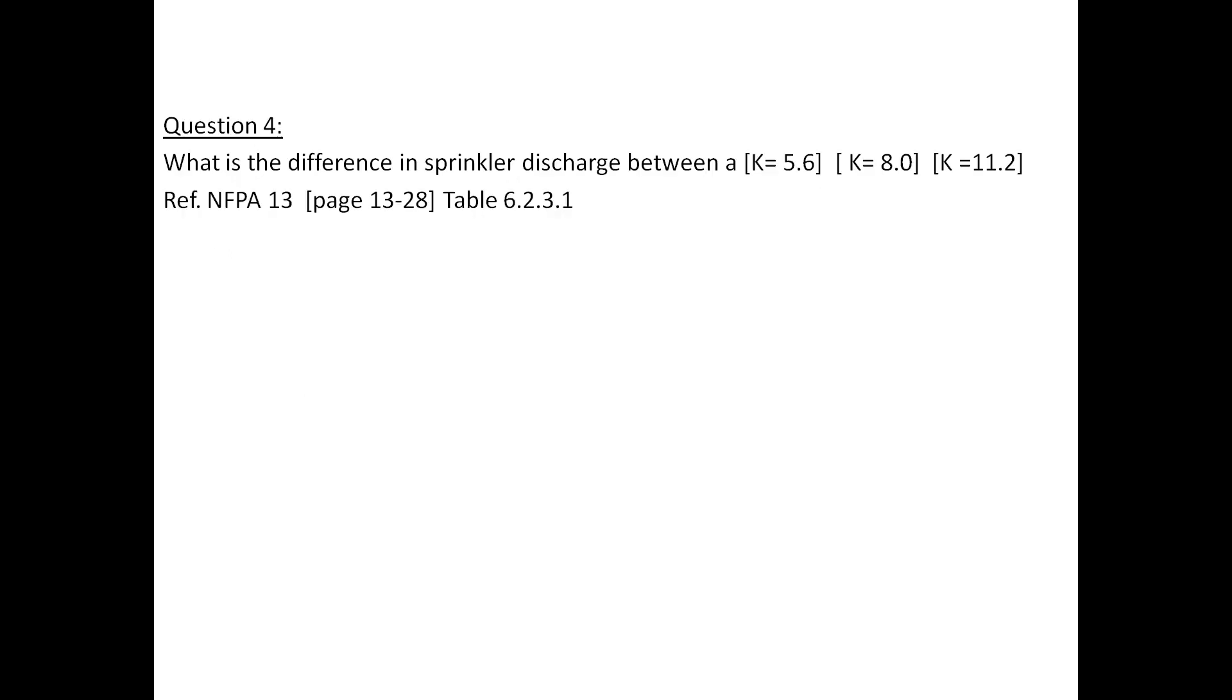Question number 4: What is the difference in sprinkler discharge between a K equals 5.6, K equals 8.0, K equals 11.2, per NFPA 13 page 13-28 table 6.2.3.1? The answer to question number 4 is K equals 5.6 is 100%, K equals 8 is 140%, and K equals 11.2 is 200%.